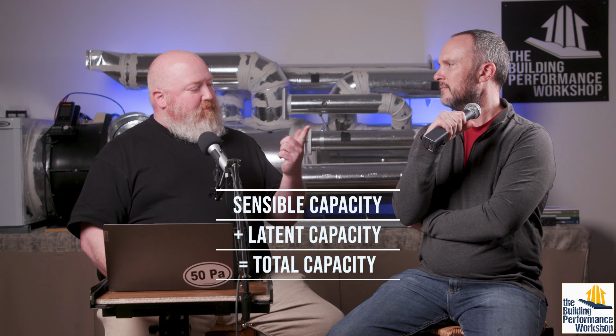So if I use that information and hit calculate, it'll give me a sensible and a latent number. Actually, it probably won't give you those two numbers directly - it'll give you a total and a sensible, or a total and a sensible heat ratio. That's easy: it's a percentage, so if it's 0.8, 80% of your total is sensible, 20% is latent.